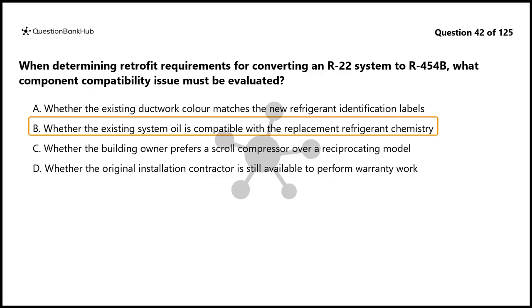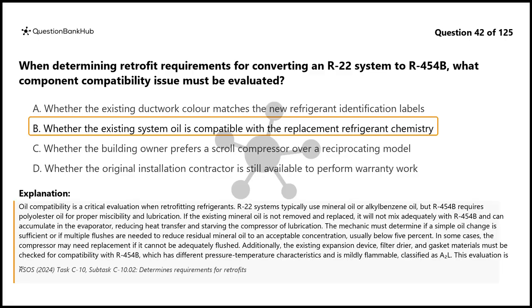The correct answer is B. Oil compatibility is a critical evaluation when retrofitting refrigerants. R22 systems typically use mineral oil or alkylbenzene oil, but R454B requires polyolester oil for proper miscibility and lubrication. If the existing mineral oil is not removed and replaced, it will not mix adequately with R454B and can accumulate in the evaporator, reducing heat transfer and starving the compressor of lubrication.